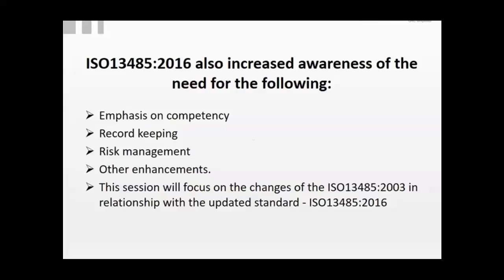And there is a way in the regulations, and I'm going to speak only for the FDA for this point because I know other countries have this as well, but the FDA has 21 CFR Part 11, which is for electronic records, electronic data keeping, electronic signatures. So it isn't like you have to keep all this data in an old locked fireproof file cabinet. I have had to do that in my past career, but you don't have to do that. That is not the requirement today. The requirement is to be able to keep those records.